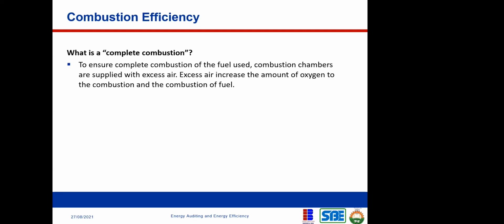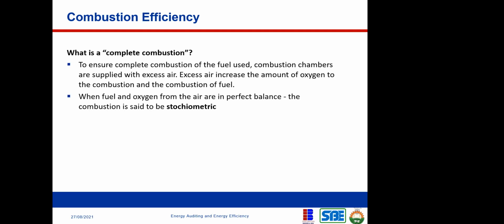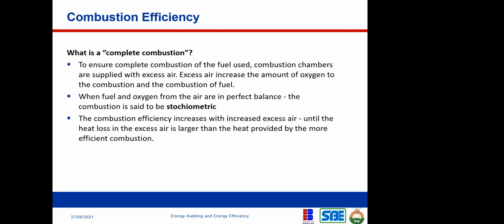Okay. So combustion efficiency. What is complete combustion? To ensure complete combustion of the fuel used, combustion chambers are supplied with excess air. Excess air increases the amount of oxygen available to the combustion of the fuel. When fuel and oxygen from the air are in perfect balance, the combustion is said to be stoichiometric. Don't mind the big grammar. What it's actually saying is that when oxygen and the fuel are in perfect balance, in perfect harmony, that's the right quantity, you're going to have a complete combustion. So when you have a complete combustion, it is known as the stoichiometric process. So the combustion efficiency increases with increased excess air.